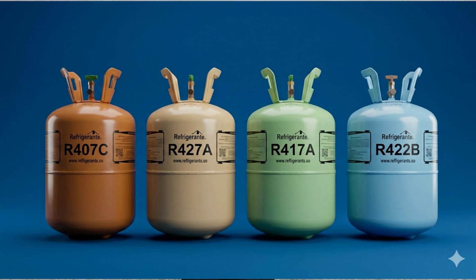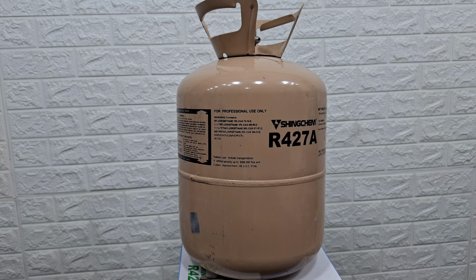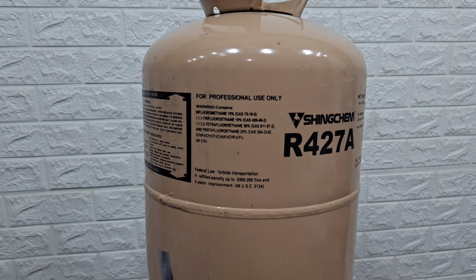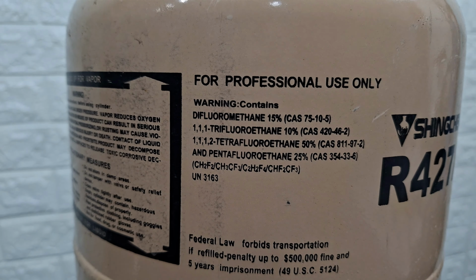On each cylinder, it is clearly written which gases are inside. But I wonder if these substitutes can really replace it completely. The biggest difference between R22 and its substitute is the presence of temperature glide. That is, you can make a freon mixture whose boiling point is like that of R22, but you cannot eliminate this temperature glide problem.